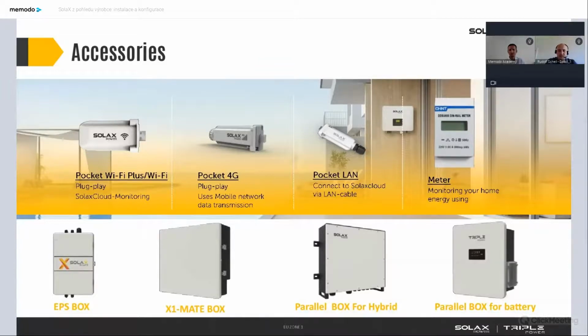Some more additional accessories, of course, is the energy meter. The energy meter itself plays a very important role, and it's absolutely necessary, especially for hybrid inverter systems with batteries. The energy meter measures the energy flow in the house, if there's a feed into the grid, or if the energy demand comes from the grid, and this information is transferred to the inverter, so that the inverter always has the information if it needs to charge the battery, discharge the battery, do nothing, or reduce the power for zero feed-in, for example. Therefore, you will always need the energy meter.